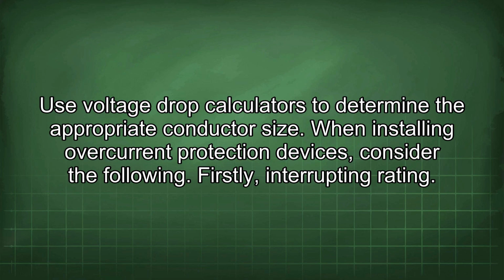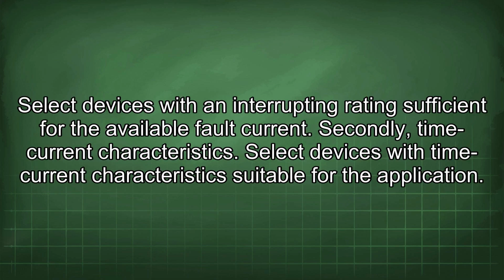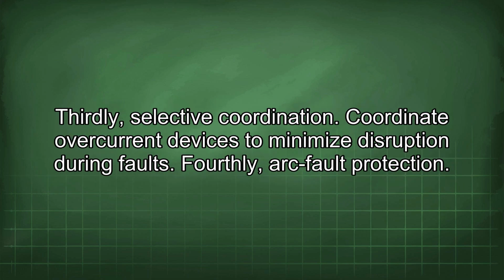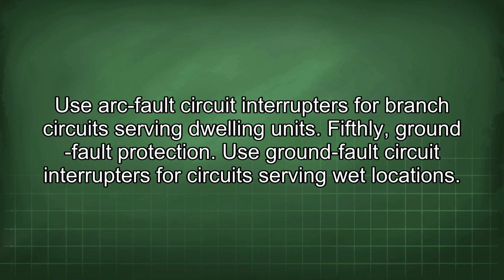When installing overcurrent protection devices, consider the following. Firstly, interrupting rating. Select devices with an interrupting rating sufficient for the available fault current. Secondly, time current characteristics. Select devices with time current characteristics suitable for the application. Thirdly, selective coordination. Coordinate overcurrent devices to minimize disruption during faults. Fourthly, arc fault protection. Use arc fault circuit interrupters for branch circuits serving dwelling units. Fifthly, ground fault protection. Use ground fault circuit interrupters for circuits serving wet locations.